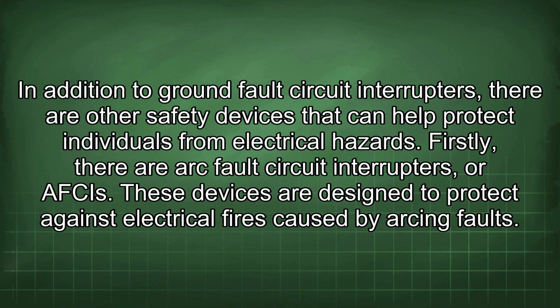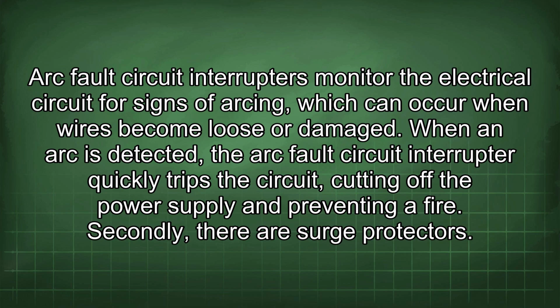In addition to ground fault circuit interrupters, there are other safety devices that can help protect individuals from electrical hazards. Firstly, there are arc fault circuit interrupters, or AFCIs. These devices are designed to protect against electrical fires caused by arcing faults. Arc fault circuit interrupters monitor the electrical circuit for signs of arcing, which can occur when wires become loose or damaged. When an arc is detected, the arc fault circuit interrupter quickly trips the circuit, cutting off the power supply and preventing a fire. Secondly, there are surge protectors.